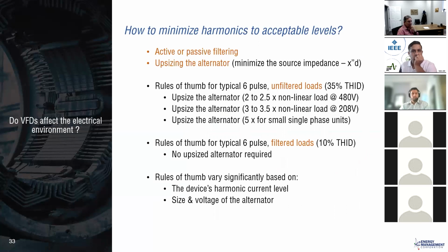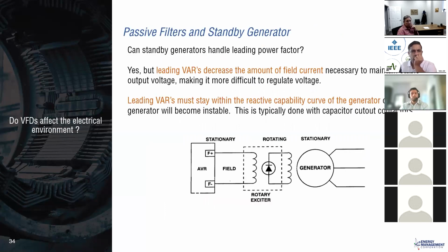And you can see that we are using typical rules of thumb here, but rule of thumb analysis varies significantly with the type of non-linear device and the alternator's voltage configuration and general size range. So rule of thumb works generally, but we should be cautious of that. That's what we should be aware of. So we say that we need to have passive filters, right? When we have passive filters, we should be worried about the leading power factor.